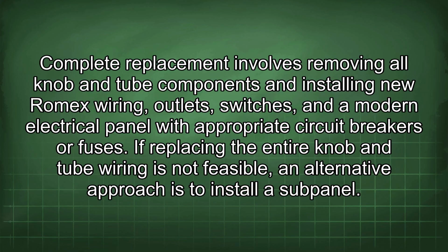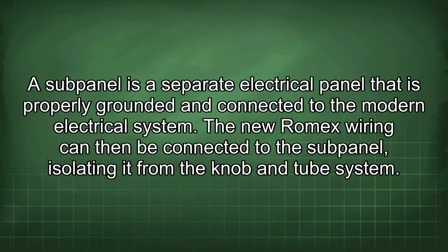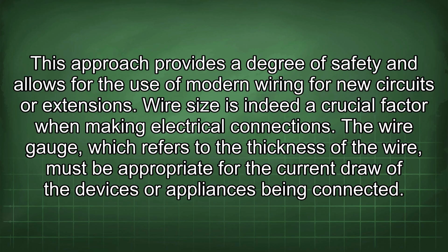If replacing the entire knob and tube wiring is not feasible, an alternative approach is to install a subpanel. A subpanel is a separate electrical panel that is properly grounded and connected to the modern electrical system. The new Romex wiring can then be connected to the subpanel, isolating it from the knob and tube system. This approach provides a degree of safety and allows for the use of modern wiring for new circuits or extensions.